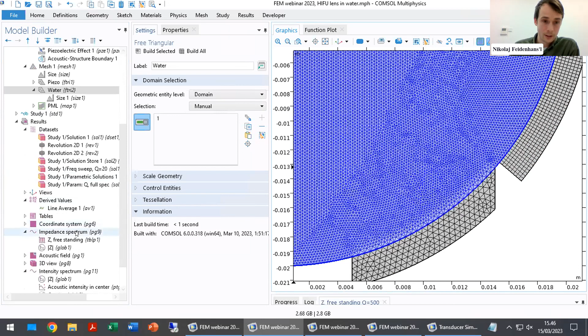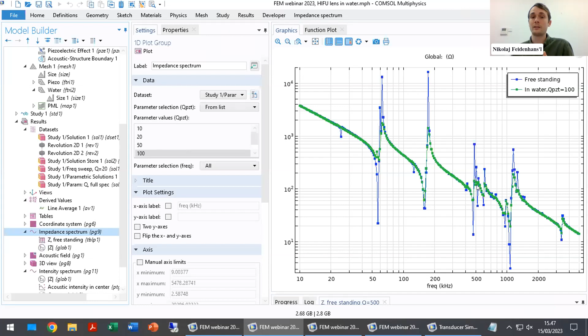results. So let's see the impedance spectrum. Okay, so then we do the simulation at all the different frequencies, and we plot the impedance spectrum based on this. The blue is the one I showed before, just the freestanding one. Then we put in the water. We see that what it mainly does is that it simply dampens all the resonances. So if we zoom in here on the thickness mode we're interested in, we can see the green one is much lower impedance value, which means less vibration and lower intensity.